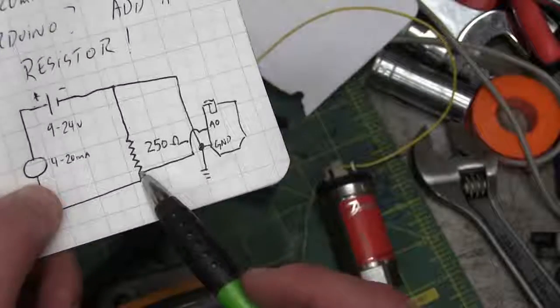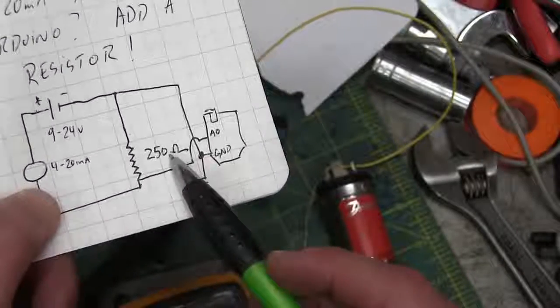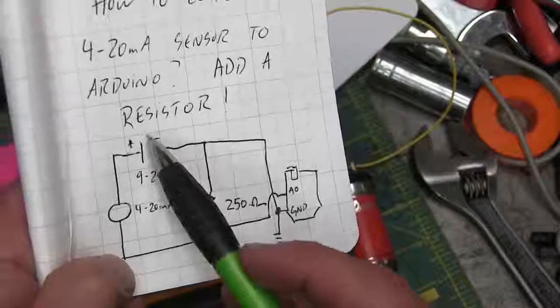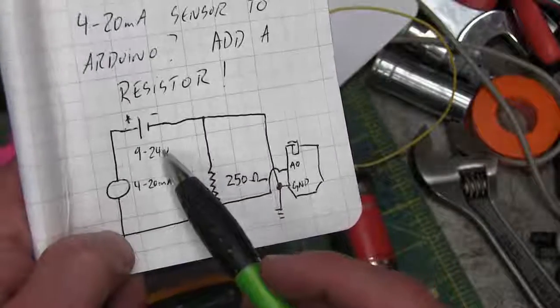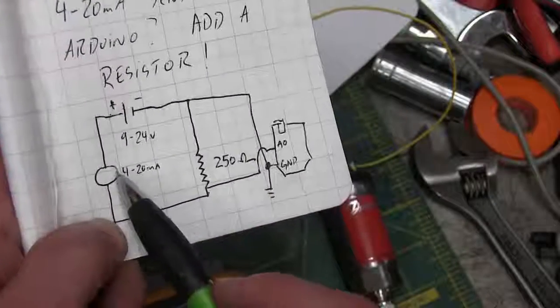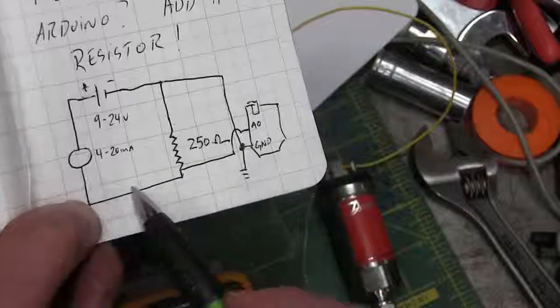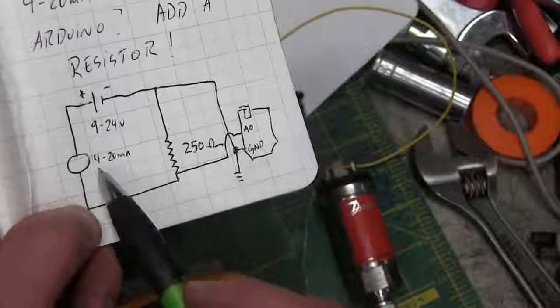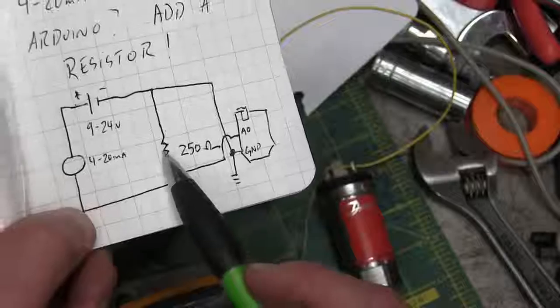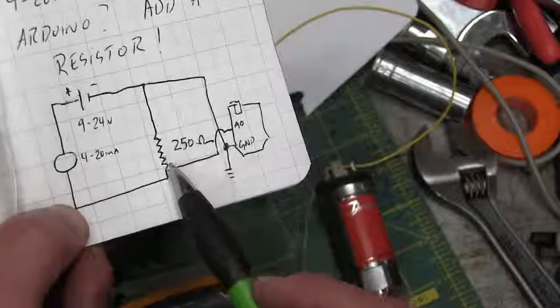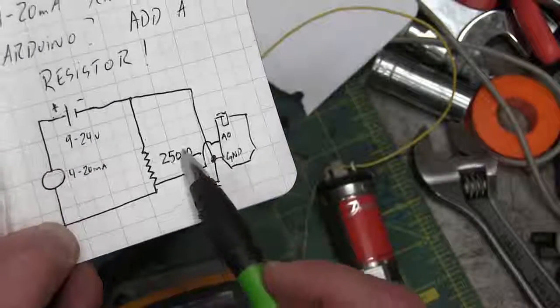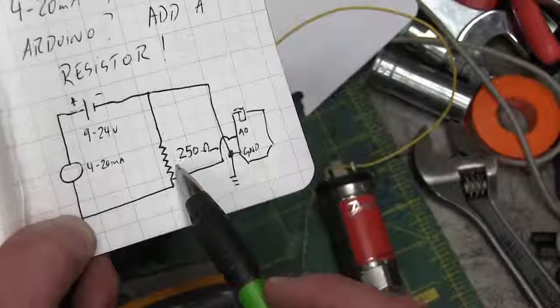All you got to do is add a voltage drop resistor, 250 ohms. We have whatever battery, doesn't matter, goes into the sensor itself. Then through here, whatever amperage is going through here will have a certain voltage drop. You got to size this so it's a maximum of 5 volts voltage drop.